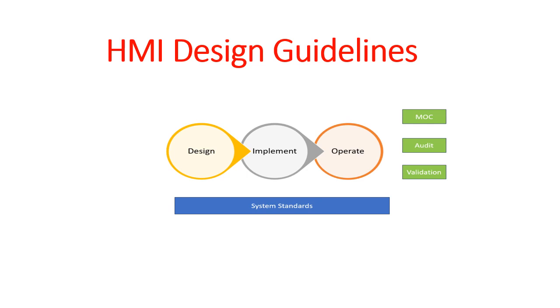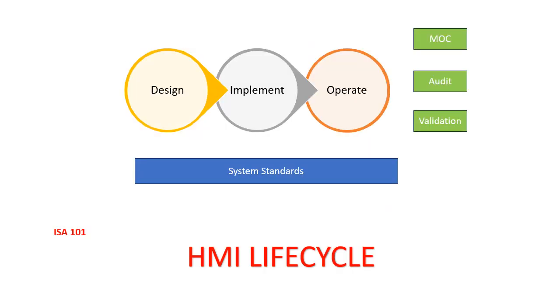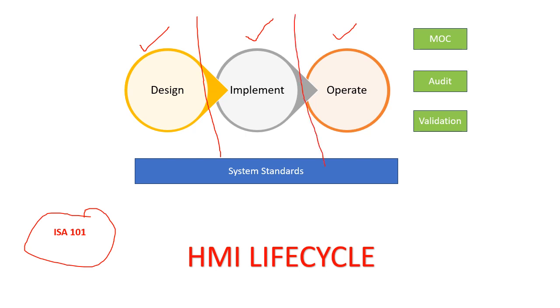In this particular lecture, we will be discussing that standard and how it provides guidelines about HMI design. The standard is ISA 101, and it provides guidelines about the HMI lifecycle. It has defined the lifecycle into three different phases: design, implement, and operate, and provides guidelines for each section. There is also a set of system standards that needs to be developed so that the same standard can be followed for all three phases of the lifecycle.